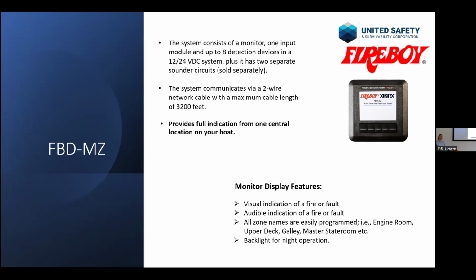Same 8 detectors per zone. This one's got 2 separate sounder circuits. A little bit different display. It actually comes up with a text that says zone 1, and you can give it its description. And then it comes out with a default all alarm for each zone. You can also put a screensaver, you've got a mute button. So it's got a little bit more functionality than the basic 2-zone system.